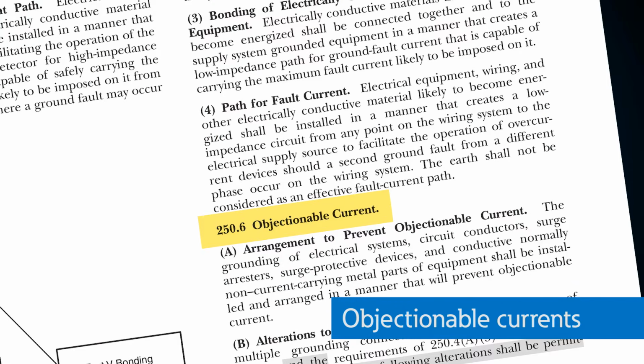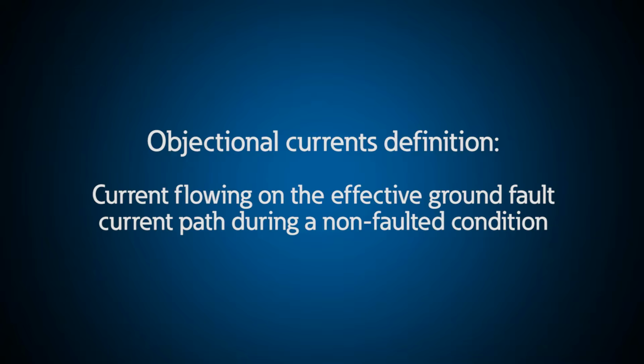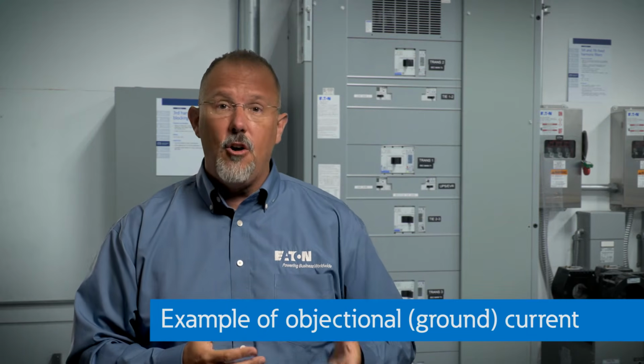All right, last statement about grounding, objectionable currents. Now, we use this term objectionable currents in Article 250 of the National Electrical Code, but there's no definition in the NEC. And when there's no definition, you know what you do? You make it up. So this is my definition: current flowing on the effective ground fault current path during a non-faulted condition. And I think to best understand this, let's talk about an example that you are probably well aware of because it received a lot of attention over at least the last 2 cycles in the National Electrical Code. And these are those motion sensor type switches that you'll find in either residential homes or commercial buildings, where you walk into a room and it turns the light on.